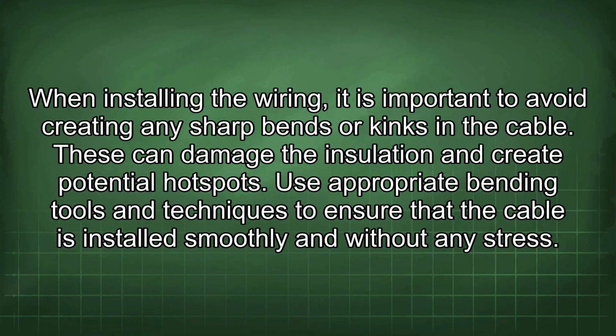When installing the wiring, it is important to avoid creating any sharp bends or kinks in the cable. These can damage the insulation and create potential hotspots. Use appropriate bending tools and techniques to ensure that the cable is installed smoothly and without any stress.